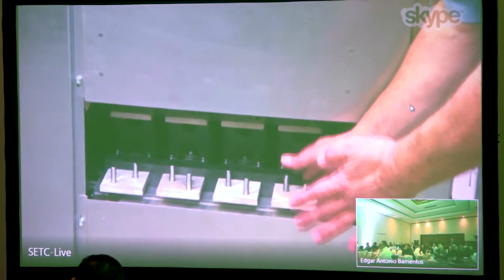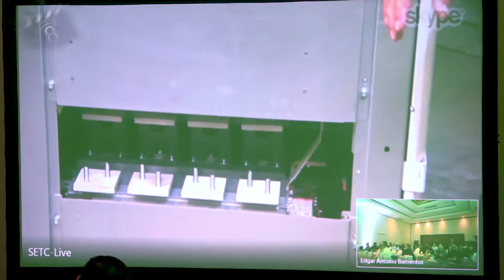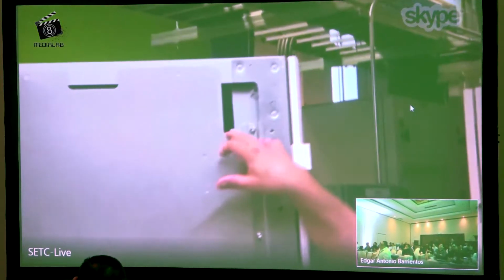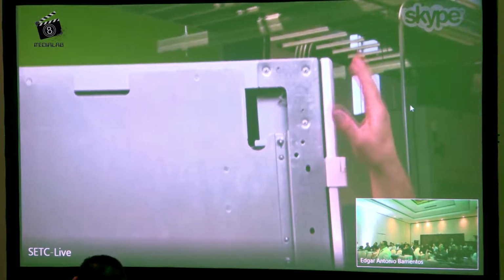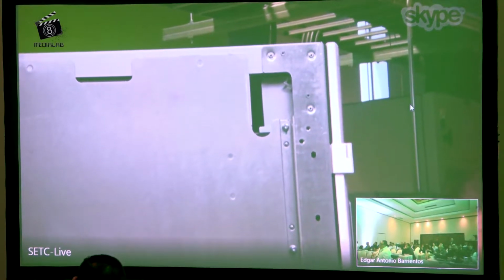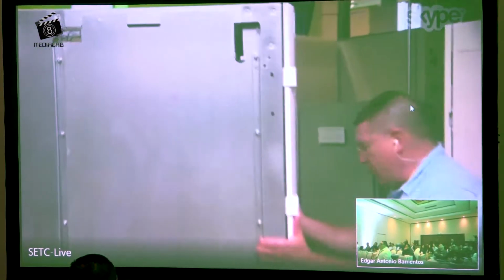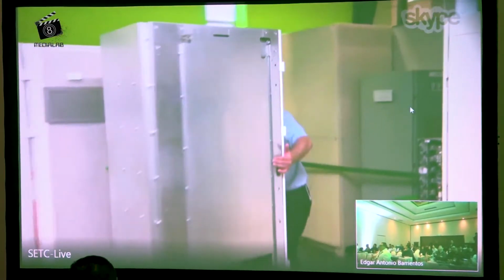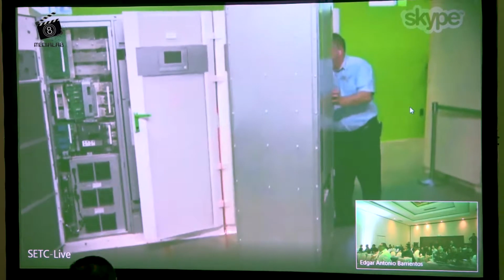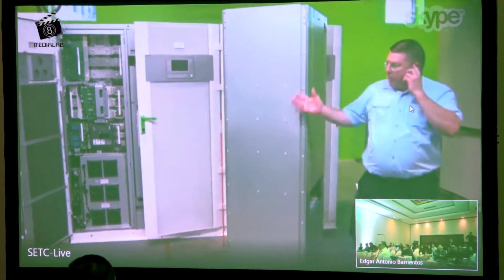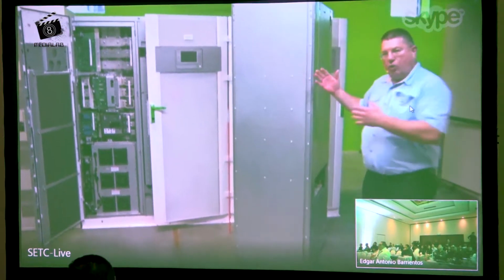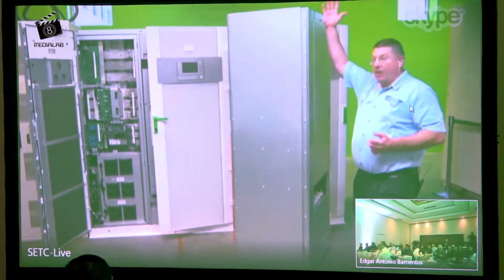We have bus links that the field service engineers install. The second interconnection is at the very top, where the fiber optic cable connects the power cabinet controller to the main controller. That's it. Let me spin this so you can see the back side—there's no need for rear access. Cooling air comes in the front and goes out the top.